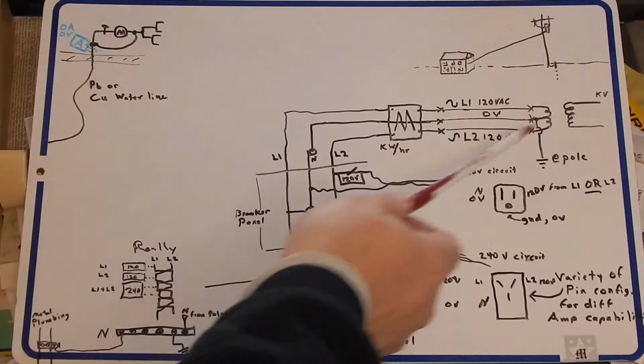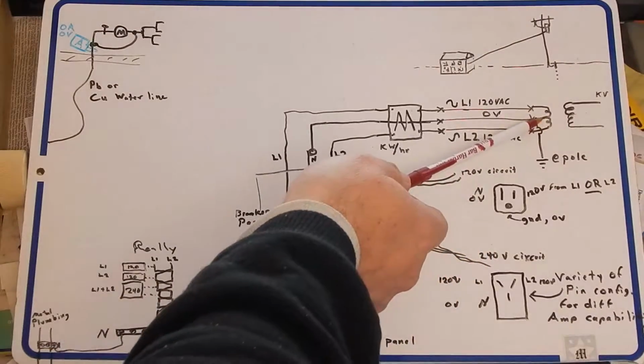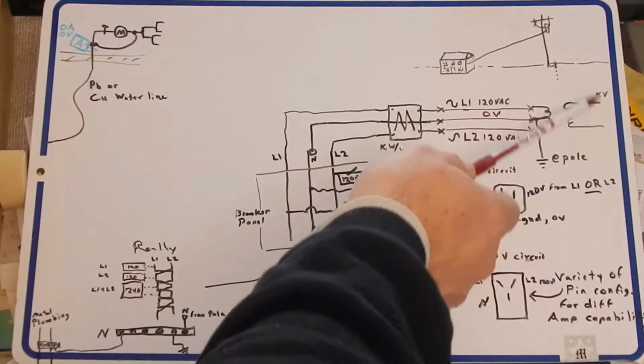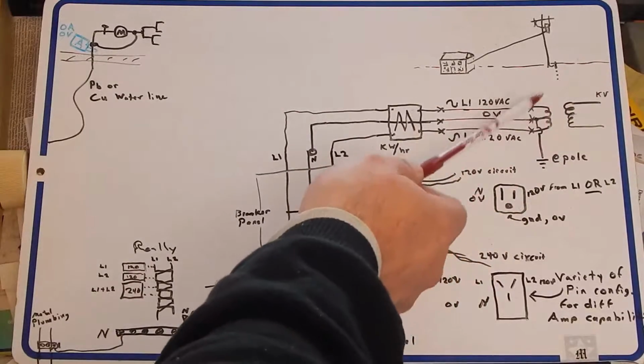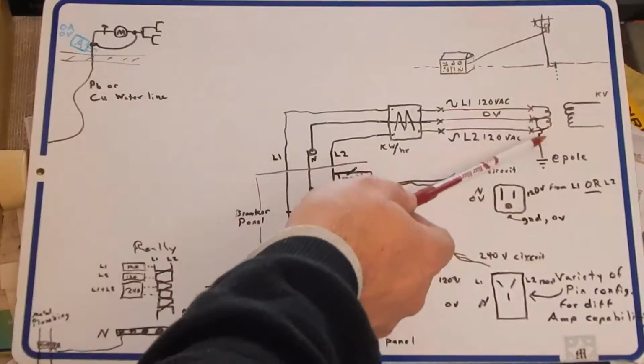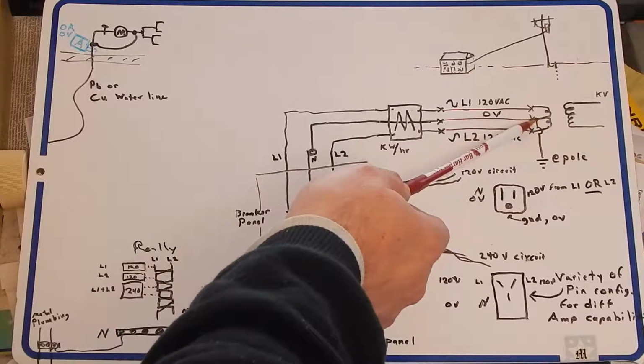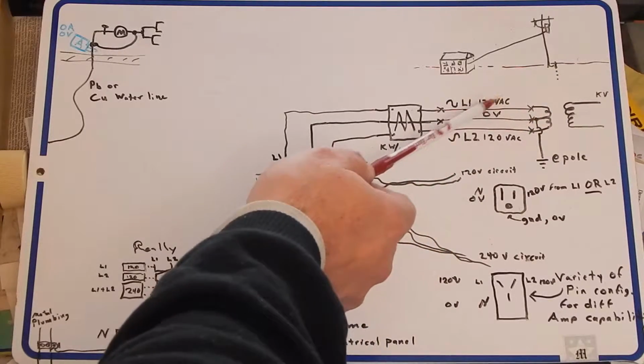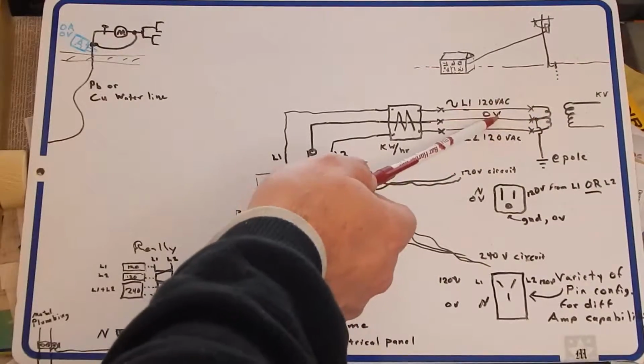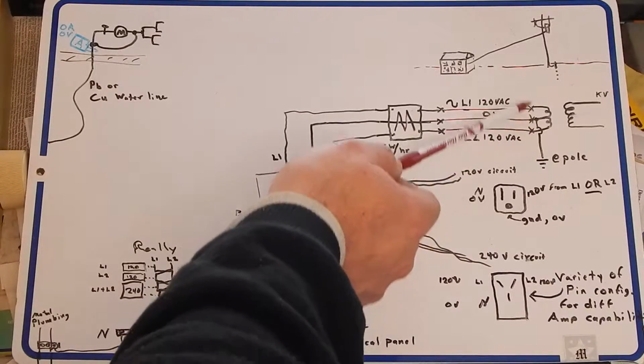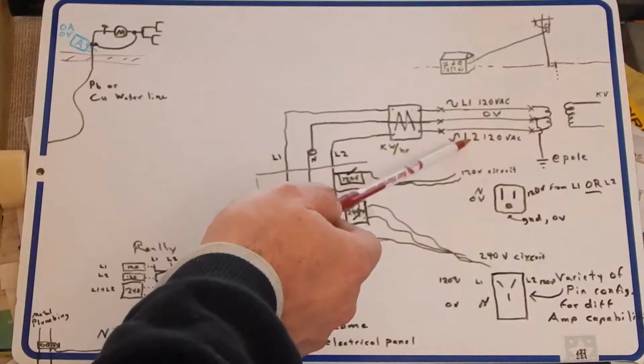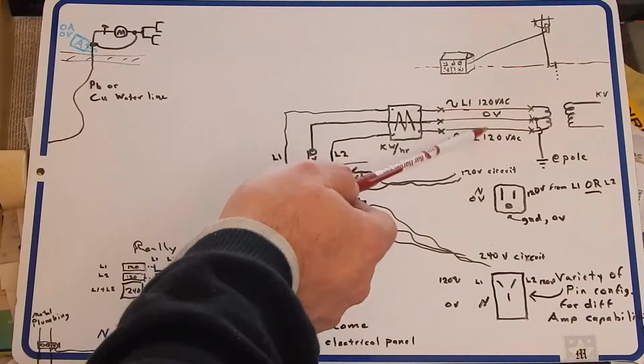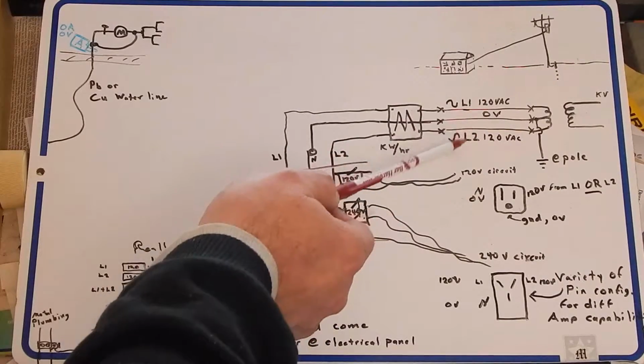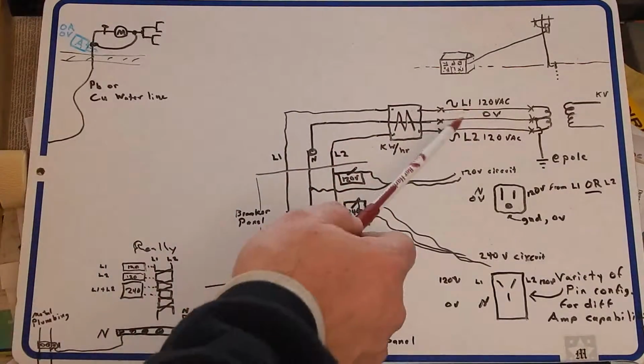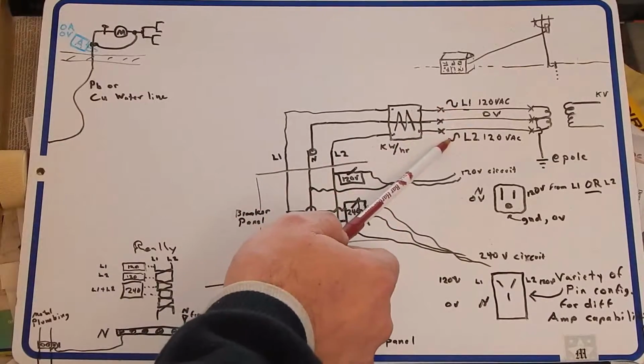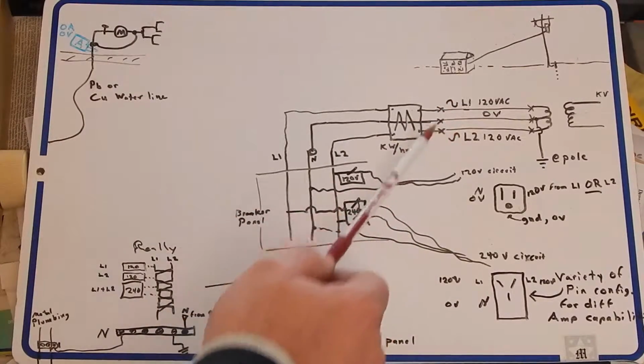Anyways, you've got a hot line. You've got what's basically a center tap transformer. You got the hot side with some kilovolts in. The output side is a 240 volt transformer with a center tap. So you've got 120 volts if you go from the center tap to one of the hots, the L1 or the L2, you've got 120 volts. If you go from L1 directly to L2, you've got 240 volts, because these are 180 degrees out of phase.